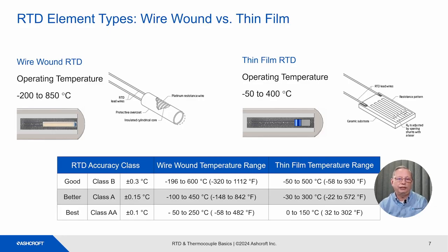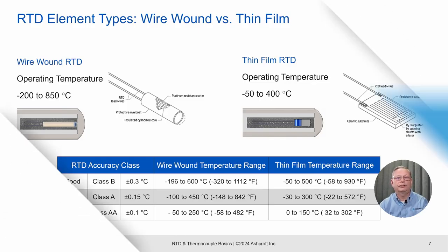To better understand the relationship of accuracy to temperature range, an example for a wire wound RTD rated Class AA would have an accuracy of plus or minus 0.1 degrees C from minus 50 to 250 degrees C, plus or minus 0.15 degrees C from minus 100 to minus 51, and from 251 to 450 degrees C, plus or minus 0.3 from minus 196 degrees C to minus 101, and from 451 to 600 degrees C.